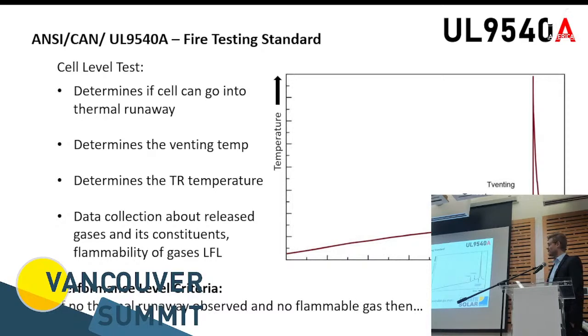So at every level, the cell, the module, the unit, and the installation, you will have a certain performance criteria. And if you pass that, then you don't have to go to the next level. So the best solution would be in the industry, which is not the case right now, if a manufacturer can pass on the cell level, they don't have to do the unit and the module and all of that afterwards, because they're already super safe on the smallest increment that represents the risk in that system.